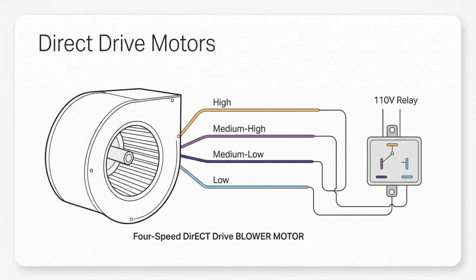These often come with multiple speed taps, like high, medium, and low. For a single speed setup, you just wire one tap and cap the rest. But if you need two speeds, say a low speed for continuous circulation and a high speed for heating, you can use a relay to automatically switch between the taps when the thermostat calls for heat.